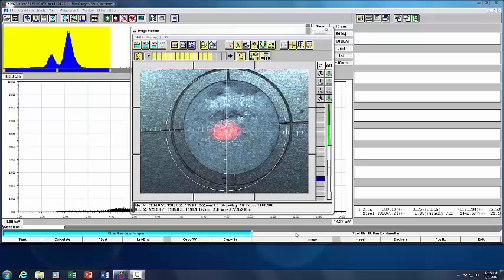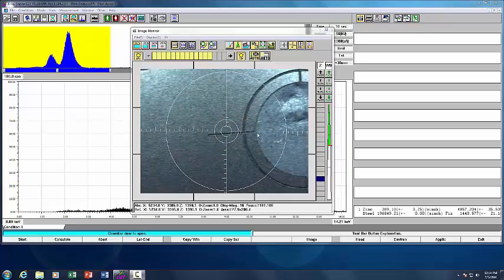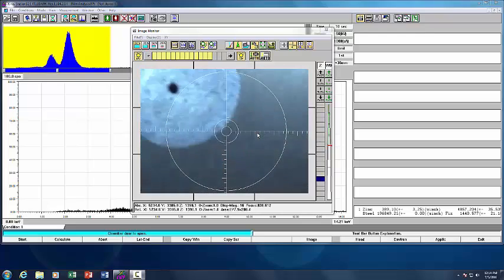Let me now show you autofocus and auto approach. We have two samples on the stage to simulate different focal heights required. One is 1 inch higher than the other. This is the lower sample. You can see it's already in focus. Let me slide it over to the 1 inch higher sample.